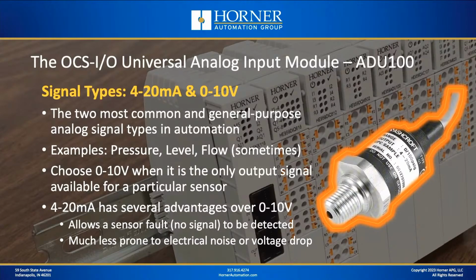Well, it has some advantages. First of all, if you have a sensor that fails or a wire that comes loose, you'll be able to detect in 4 to 20 milliamps that you've got a signal below 4 milliamps, which means you've got a problem. Whereas if you have a 0 to 10 volt sensor that fails, 0 volts doesn't really tell you anything because 0 volts is a valid reading. Also, from an electrical noise standpoint, 4 to 20 milliamp, because it's a current, is much less prone to noise or voltage drop.